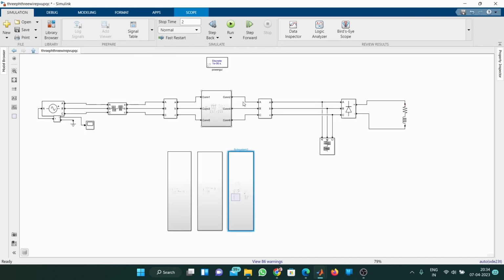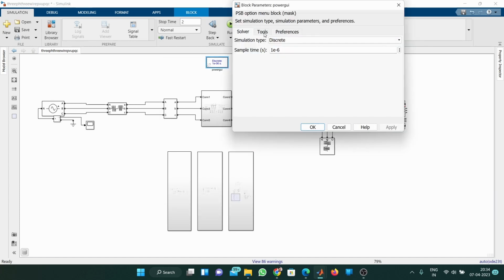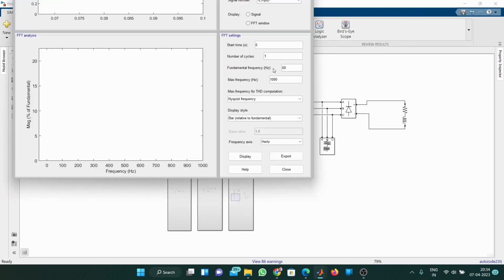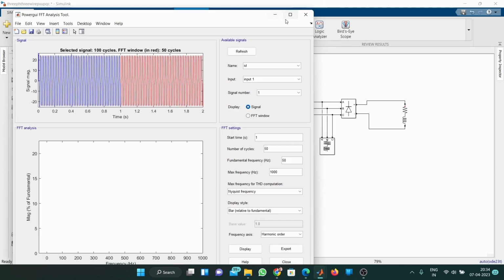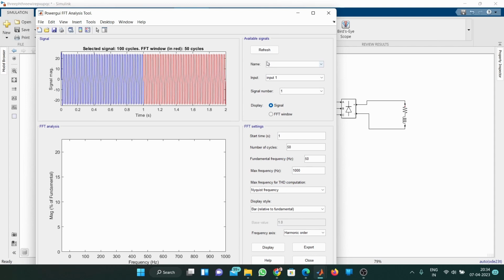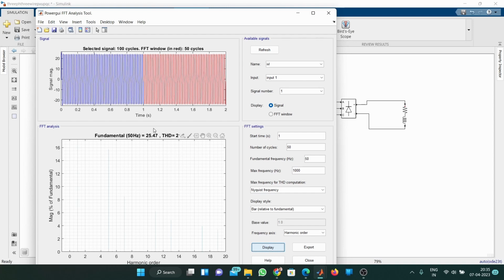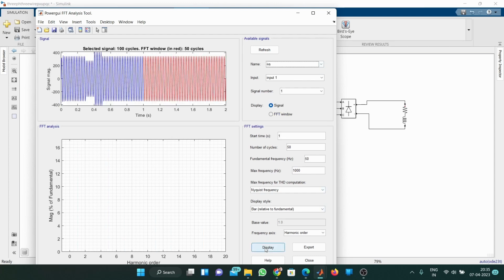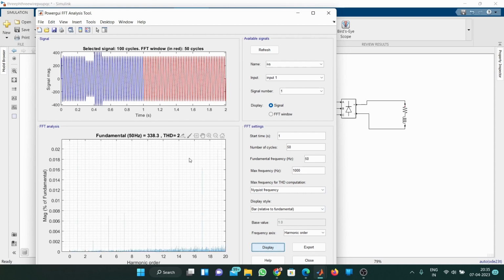Now we will see the reduction in harmonics. We will see the FFT analysis on the load side current, and then the FFT analysis on the source side current. I have given the name for the load side current as IVL. Now we will display the harmonic analysis. As you can see here, the THD in the load current is 21.48%. Now we will see the source side. I have taken the name as IVS. Now we will display the harmonics on the source side. Now it is reduced to 2.48%.